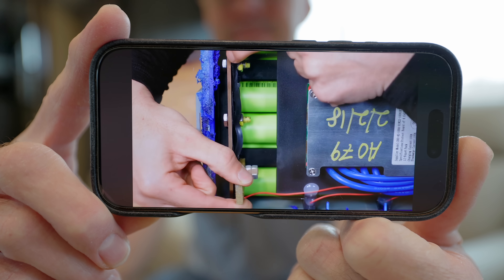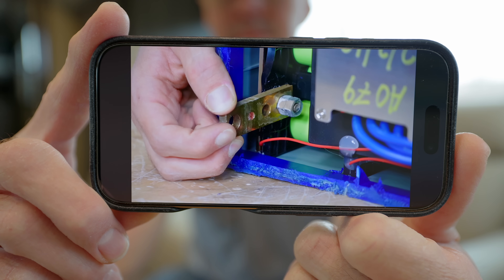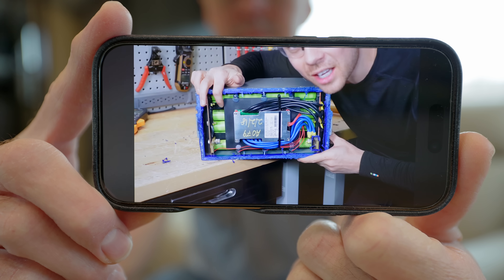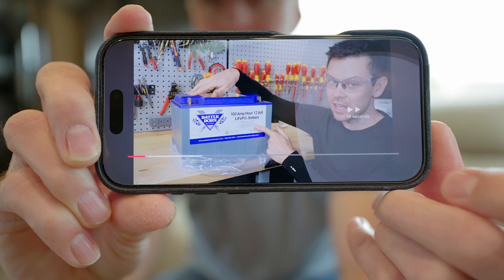What he found is damage inside the battery from the bus bar through a bolt and a piece of plastic to the terminal on the battery. It's evident that the plastic is deformed from heat, which made the connection even more loose, creating even more heat. At that point, that battery's not safe anymore. The story continues because we have a response from Battleborn and additional testing on new Battleborn batteries, which actually opened up another can of worms.